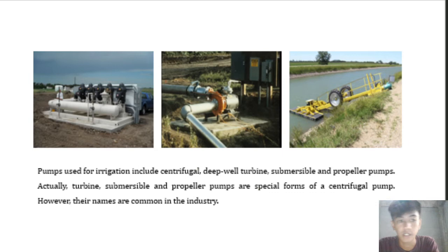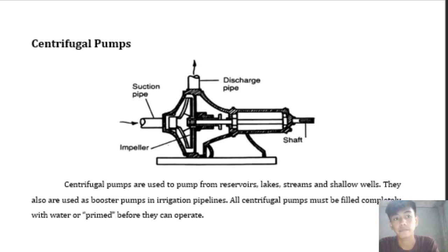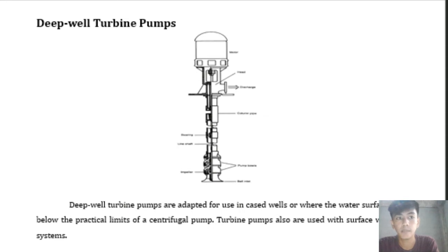Pumps used for irrigation include centrifugal, deep well turbine, submersible, and propeller pumps. Turbine, submersible, and propeller pumps are special forms of centrifugal pump, though their names are commonly used in the industry. Centrifugal pumps are used to pump from reservoirs, lakes, streams, and shallow wells, and are also used as booster pumps in irrigation pipelines. Deep well turbine pumps are adapted for use in cased wells or where the water surface is below the practical limits of a centrifugal pump, and turbine pumps are also used with surface water systems.